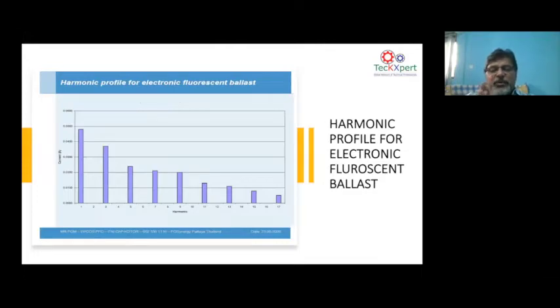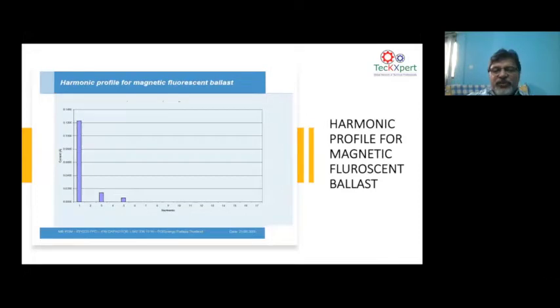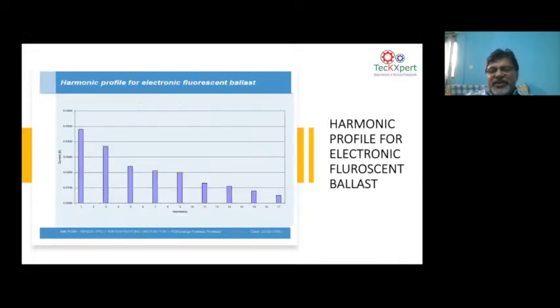Okay, now here you have an electronic ballast, which I just said before. The fluorescent CFL uses an electronic ballast, which again is an SMPS. It is very similar to the wave shape that you saw in the first slide, 2 pulses in the time domain. As with the frequency spectrum of the previous one that I showed, which was about a fax machine or a computer, a CFL also looks more or less the same. It is more of 3, 5, 7. That means in an office environment, you have all those third harmonics predominantly happening because of your lighting systems as well as your office equipment.